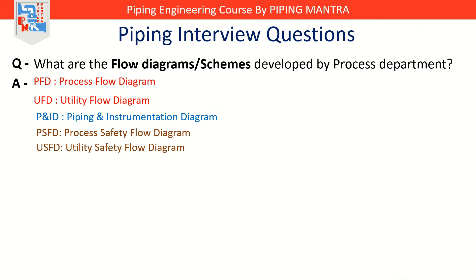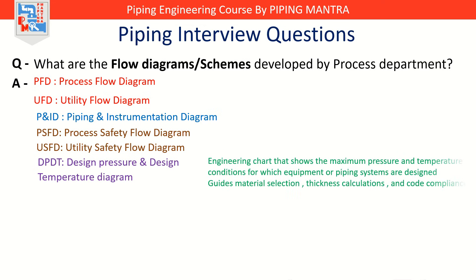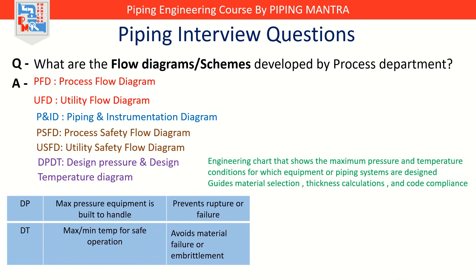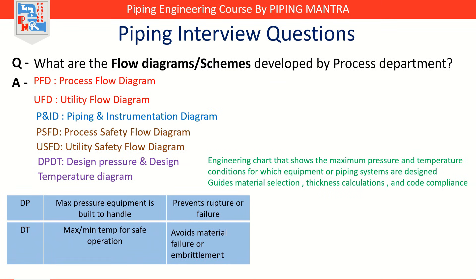Fifth is DPDT, that is Design Pressure and Design Temperature Diagram. The DPDT diagram is like the limit chart of your process equipment. It shows the maximum pressure and temperature each piece of equipment or piping system is designed to handle. This is vital for selecting materials, calculating wall thickness, and meeting codes like ASME. It sometimes even includes normal operating conditions for easy comparison.